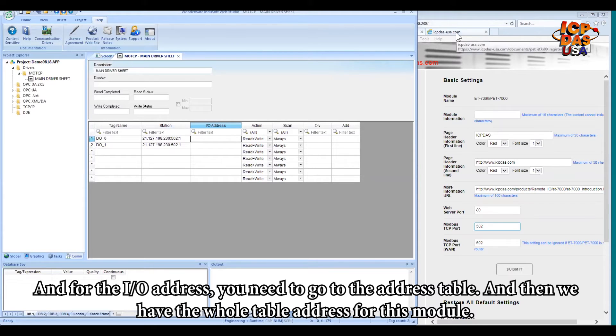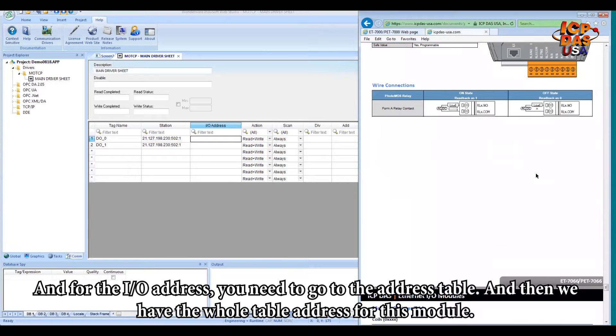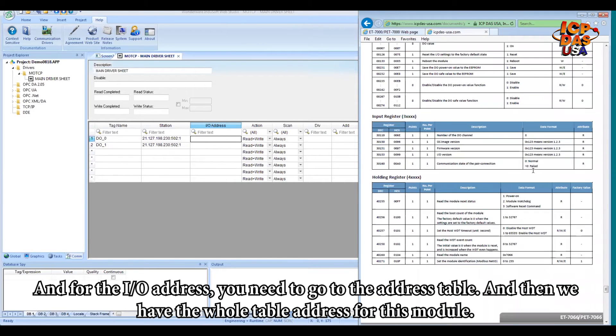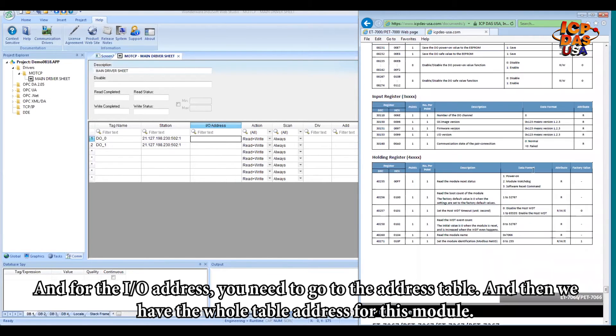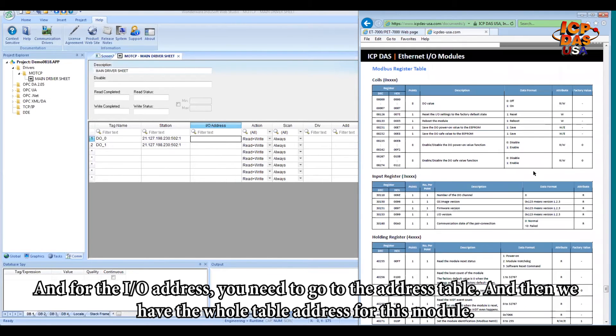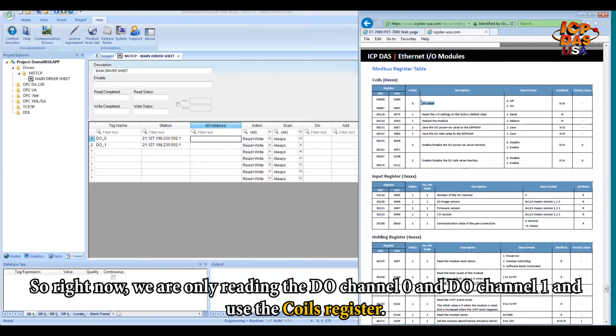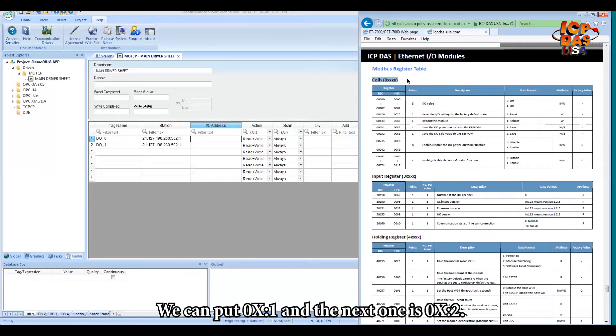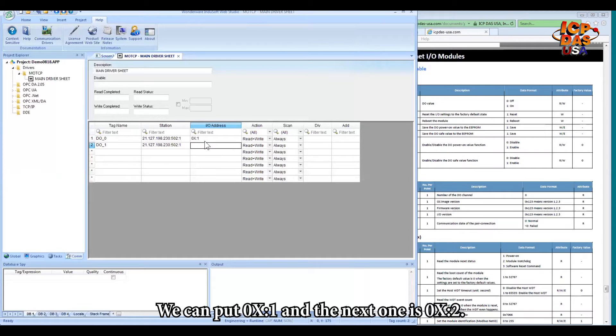And for the I/O address, you need to go to our address table. And then we have the whole table address for this module. So right now we are only reading the DO channel 0 and DO channel 1. And then we will use the coil register. We can put 0x, colon, 1. And then the next one will be 0x, colon, 2.